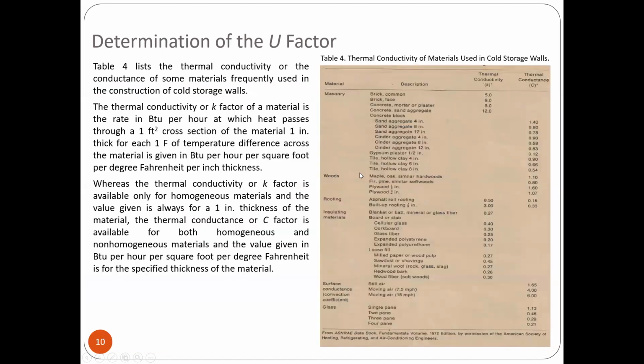Numbering. Okay? So table 4 also lists the thermal conductivity or the conductance of some materials frequently used in the construction of cold storage wall. Kung wala doon sa table 1 to 3, so mag-iisa-isa ka. I-transfer nyo. The thermal conductivity or K factor of a material is the rate in BTU per hour at which heat passes through 1 square foot cross-section of the material 1 inch thick for each 1 Fahrenheit of temperature difference across the material. It is given in BTU per hour per square foot per degree Fahrenheit per inch thick. Kasi ang thickness mo is in inches. Okay? Masonry, wood, mga materials, roofing, sa bubong. So, insulating materials, glass, meron ka. So, andyan yung mga value. Okay?